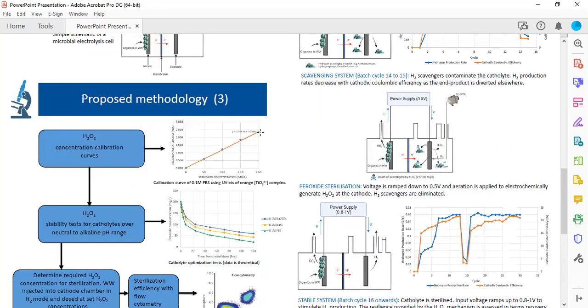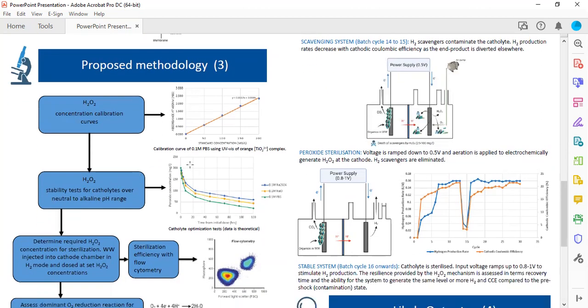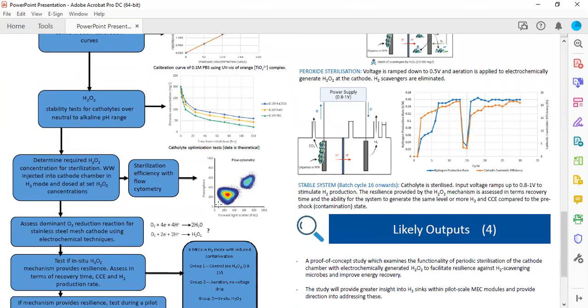So the proposed methodology is to first create a calibration curve for peroxide. The second step would be to optimize the catholyte over neutral to alkaline pH ranges by measuring the pH of different electrolytes for different pHs over time, and see how they degrade for each catholyte. And then the third step would be to inoculate 3 groups of reactors to determine the peroxide concentration required for sterilization. This will be done with stock peroxide, not the electrochemically produced peroxide. And this would allow us to identify an optimum sterilization efficiency of the catholyte with flow cytometry.